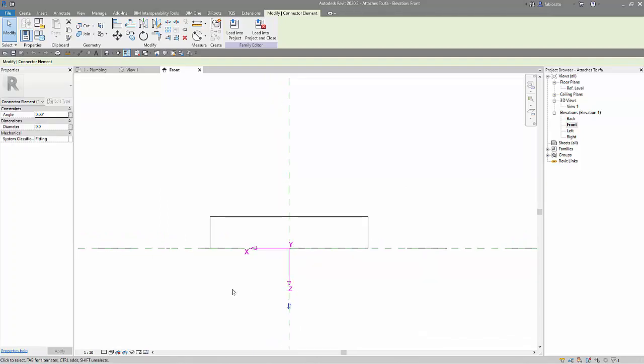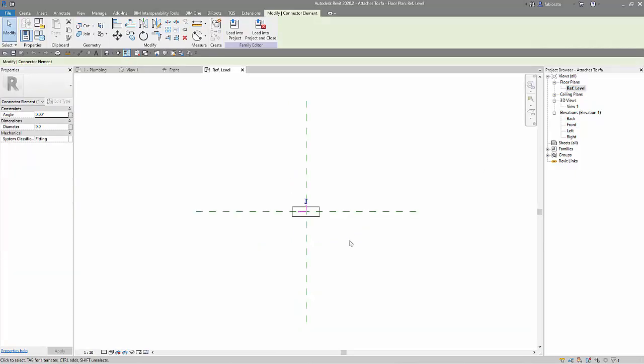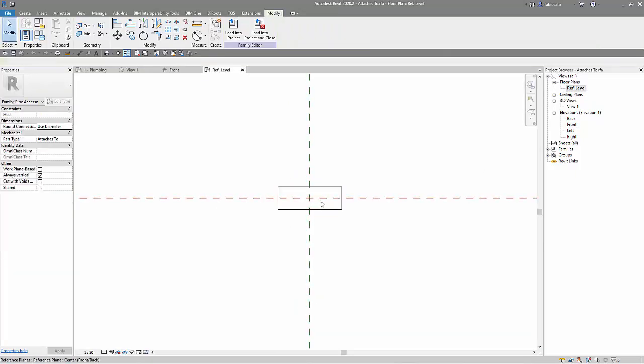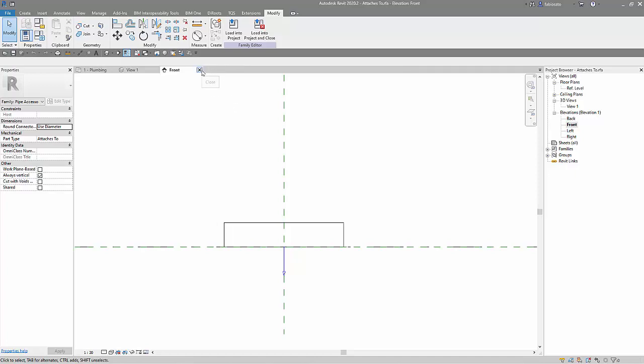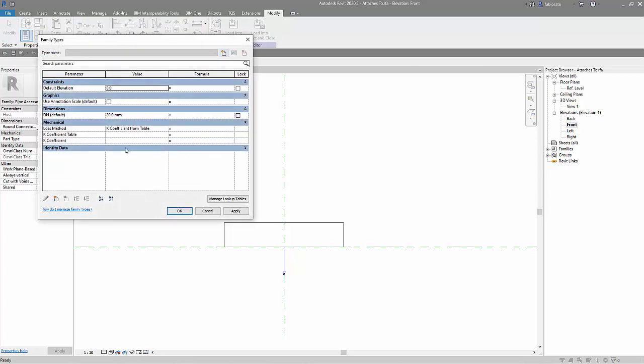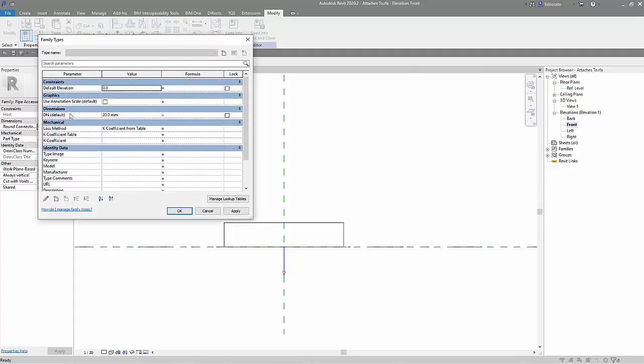Let's look at the family itself — it mainly looks like a brick, going from the reference level upward, with the connector right there. The diameter value is set to zero. It can also work if you rotate it 90 degrees so the connector is pointing to the left. What is important is that the pipe connector is aligned to the reference level. This is the main thing you should care about for an attach-to family. In the parameters there's not much to do — I created a nominal diameter parameter but it is not in use.